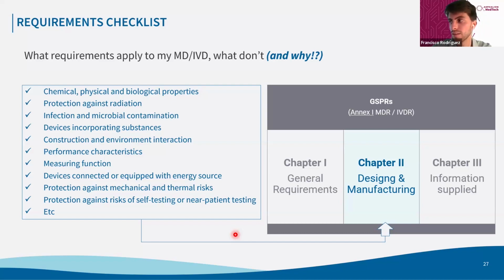If we think that a requirement is not applicable for our device, we need to provide a justification of this non-applicability, okay? So for example, there are specific requirements for devices that are provided in a sterile status, okay? So in case our medical device is not sterile, we need to justify that this requirement is not applicable because our device is not intended to be sterilized, okay?